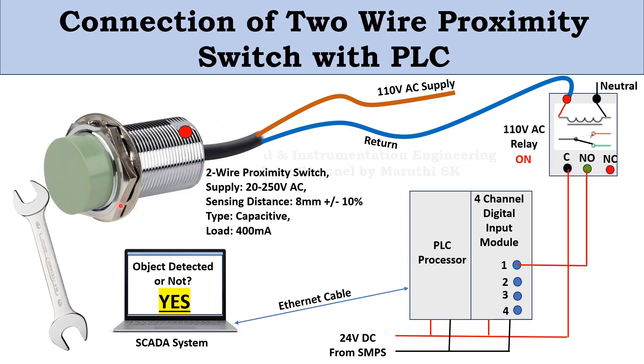In a 2-wire proximity switch, the neutral is connected to the relay coil terminal. When the proximity switch is in the off condition, neutral flows through the relay coil to the proximity switch. The proximity switch receives phase, and together with neutral through the coil, it operates. If the coil fails, the proximity switch will not work on phase alone — it requires 110V AC plus neutral through a good coil condition.